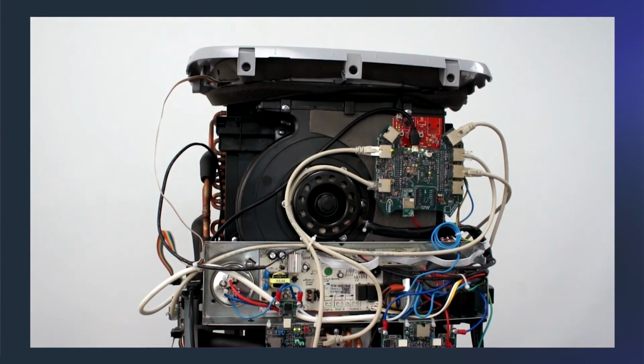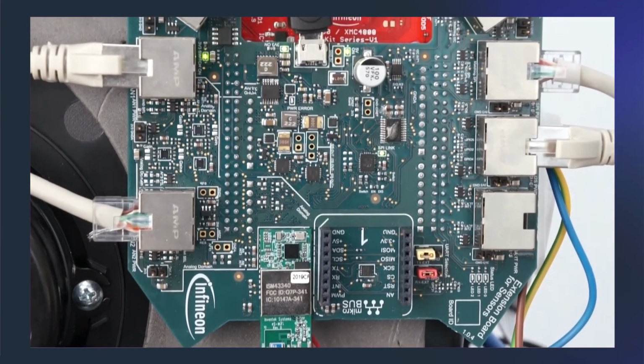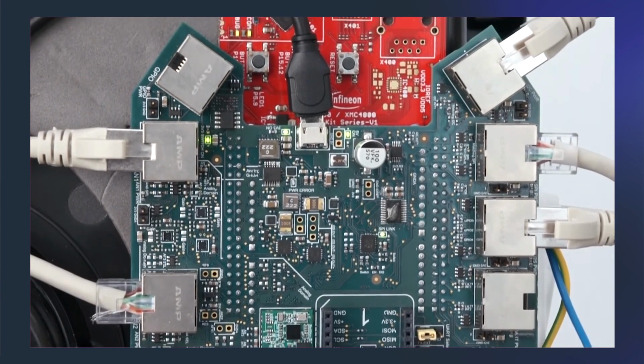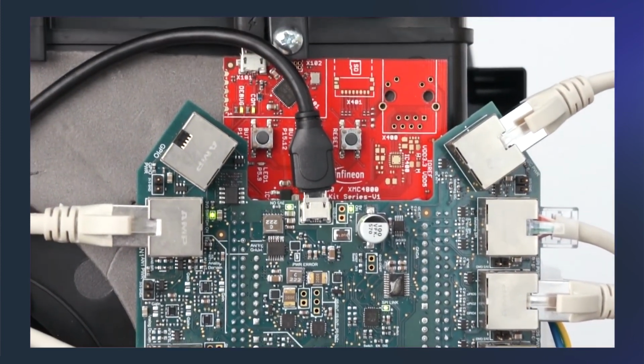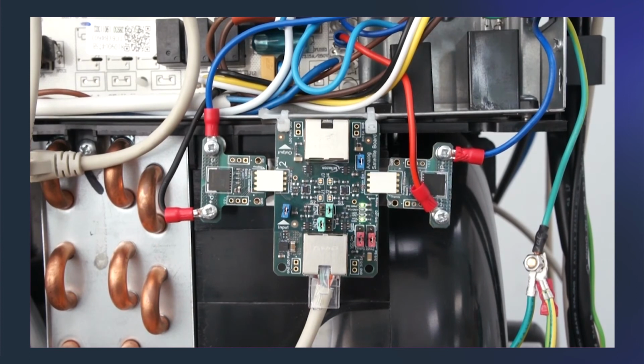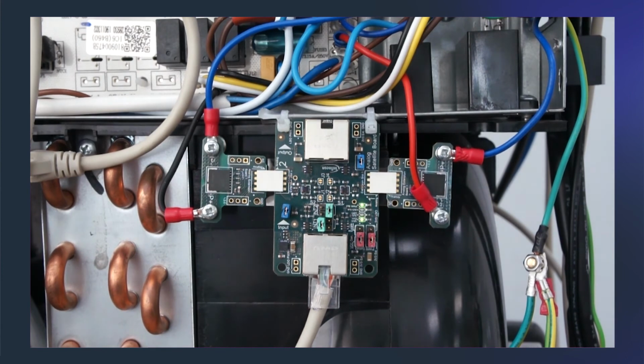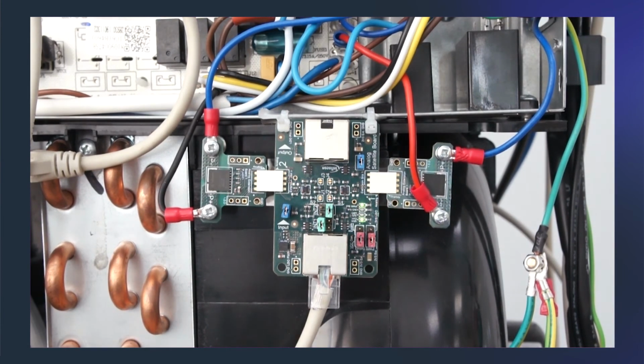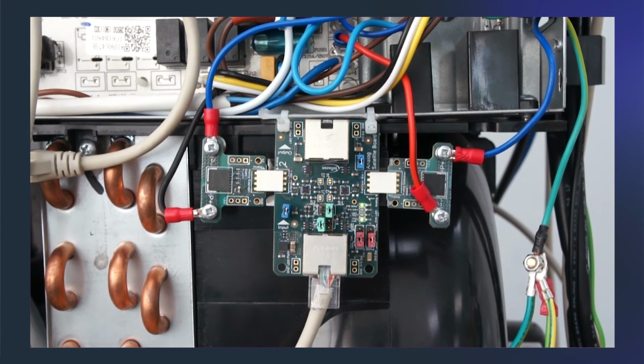Okay, so let's move on. Here is the main board extension shield that is attached to the main board. It aggregates all the sensor data that are connected to it, and it runs FreeRTOS, a real-time operating system. So we have attached several current sensors. One is used to measure the current consumed by the compressor, and the other two sensors measure the current consumed by the output fans, both cold and hot. When the average consumed current changes significantly, it means that something went wrong with the motor or a filter, or a compressor should be changed.